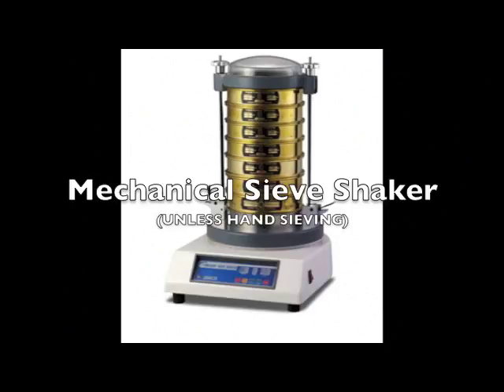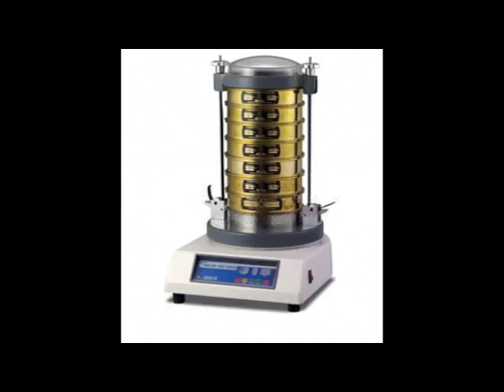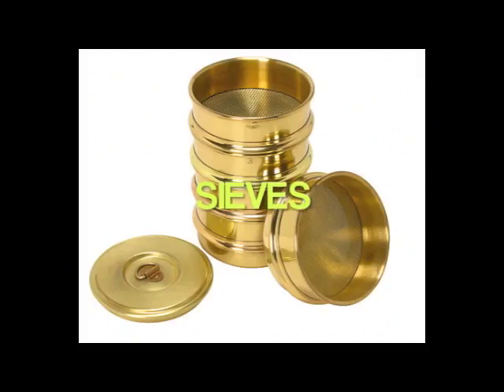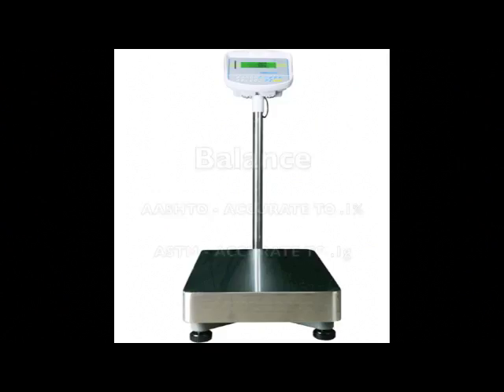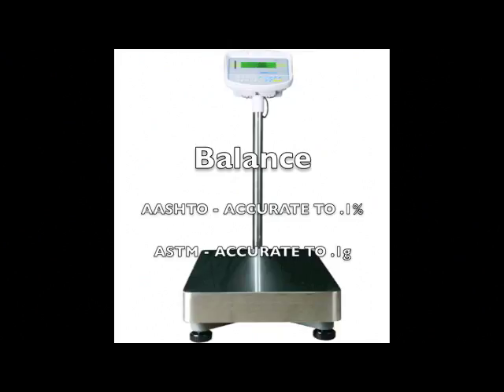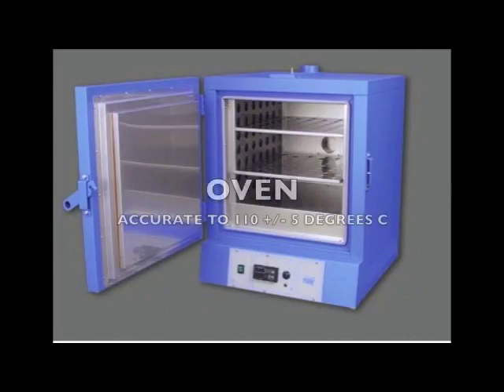To perform this test, we will need a mechanical sieve shaker unless hand sieving, a set of nested sieves appropriate for the aggregate we are testing, a balance. Both AASHTO and ASTM require that the balance be accurate to 0.1% of the expected mass, while ASTM also approves scales readable to 0.1 gram. And finally, an oven, accurate to 110 plus or minus 5 degrees Celsius.